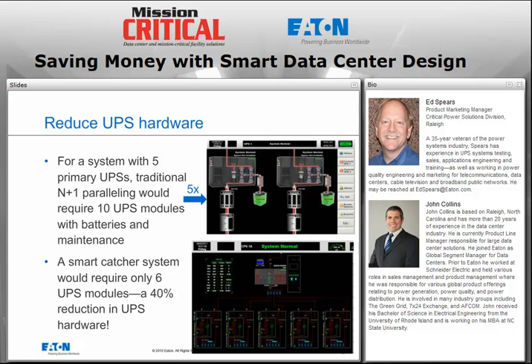And so I'd like to add to that, Ed, in that keep in mind here that Ed's showing some examples of some actual customers that we've worked with, but the intent of this presentation is to objectively talk about the concept and what's available out there for people to consider. And so the examples we're using aren't the only considerations. And what I mean by that is it is possible that the reserve UPS could even be 2 UPSs in parallel feeding a much larger bank of UPSs that are acting as primary. So you could have here 5, 6, or 7 primary UPSs and maybe one reserve UPS, you're not comfortable with that, so you put two UPSs in parallel as the reserve.